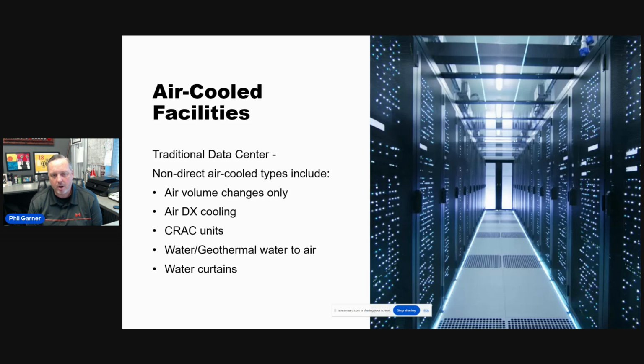The last one is a water curtain, similar to a swamp cooler or a water chiller. It's not the most effective, especially in high humid areas, and I'm not a huge fan of introducing more water and humidity to electrical components. But in certain desert applications and other places, this can be a cost-effective way of increasing that delta T to the level you need.